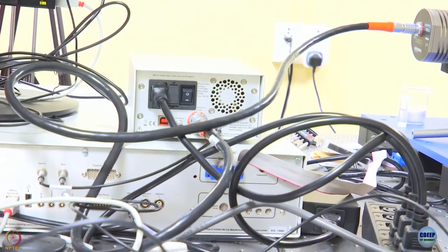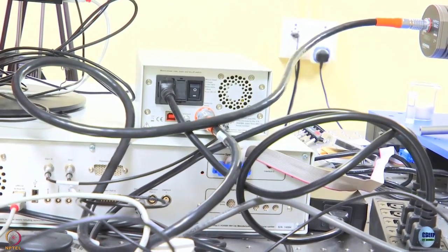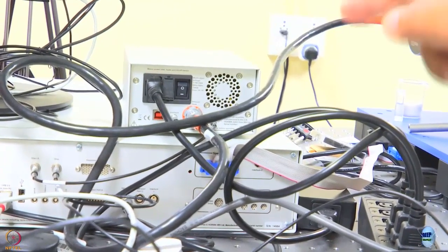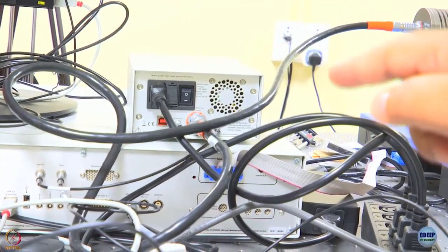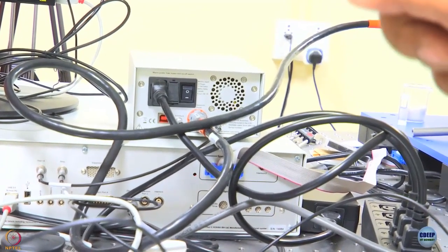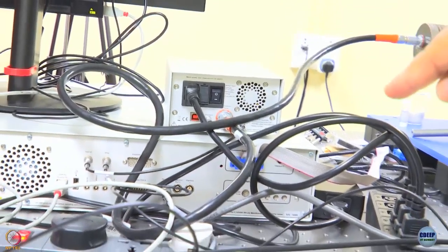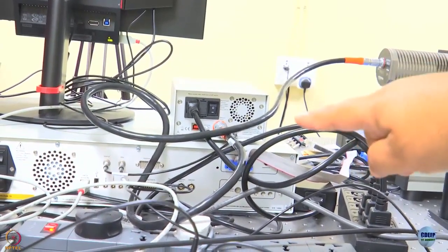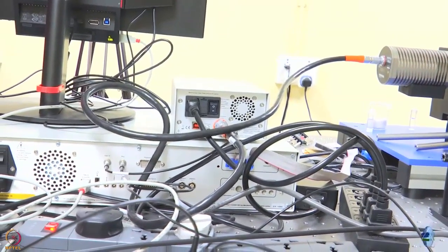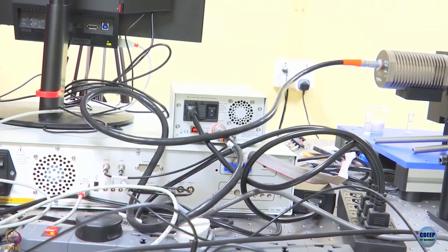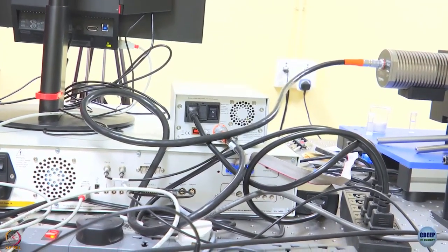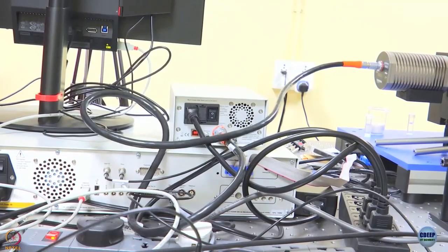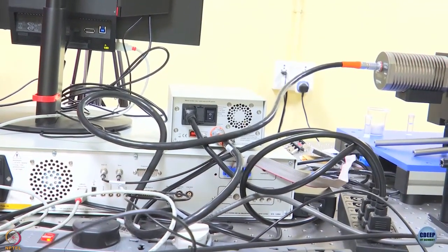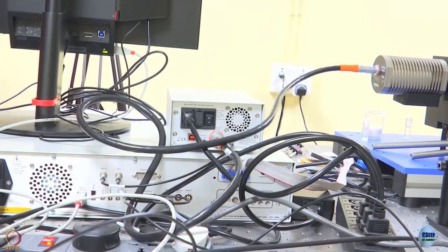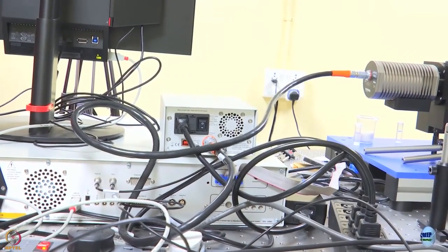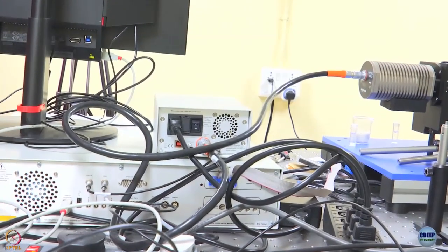So that is start. What about stop? You can see that there is another terminal there which says stop. Input for stop comes as a synchronous pulse from the laser power supply itself. Right now, we are not trying to show it to you because it is a little too circuitous, but we do have a stop which comes from the source. So, here you see we are starting the charging of the TAC by the fluorescent signal, and we are stopping by the synchronous signal. This is called reverse mode, and reverse mode is useful because especially when you do a high frequency kind of measurement, reverse mode helps decrease the dead time of the instrument and recording is fast.